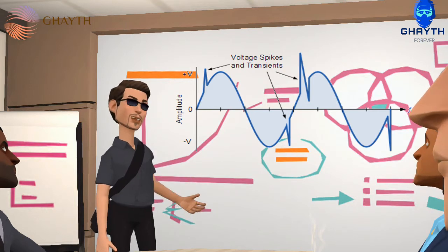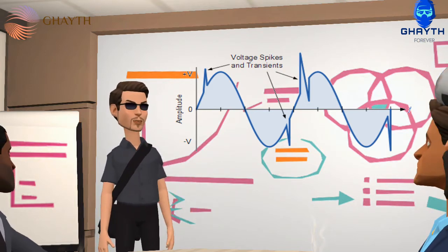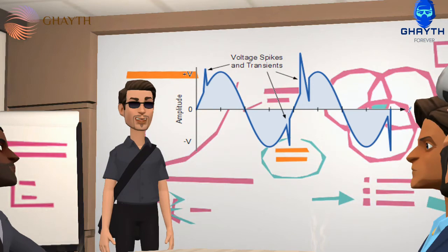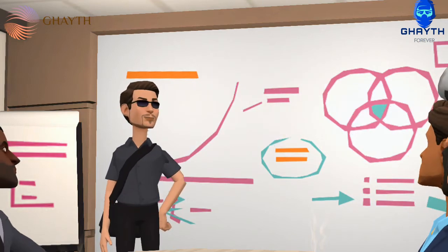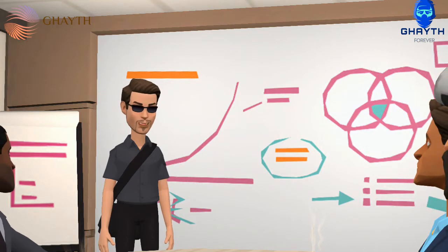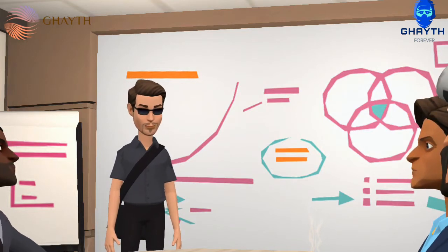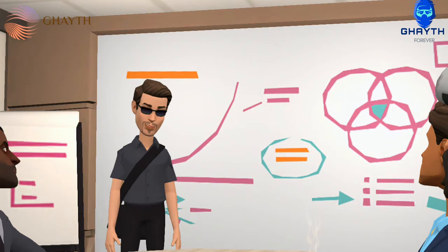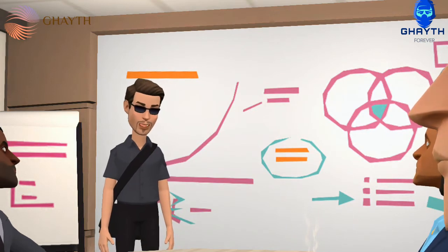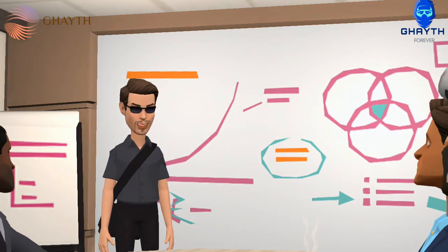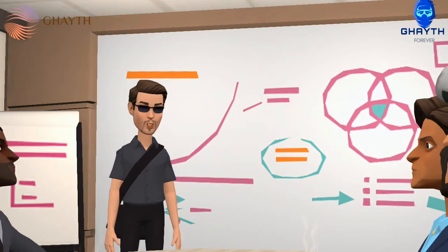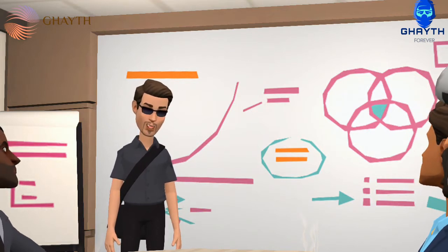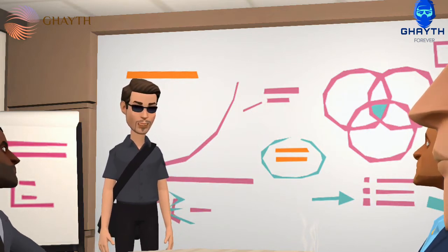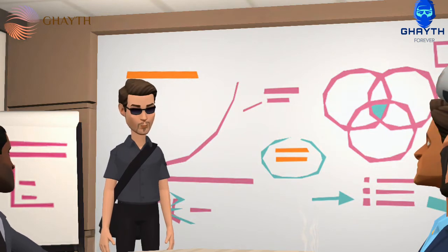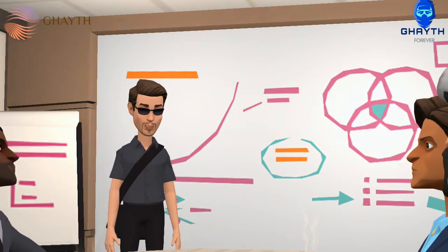However, those nanoseconds, just billionths of a second, can inflict some major damage on a machine if the surge is high enough. What usually causes a surge or spike? One of the most known causes is lightning, although it is very uncommon. More common causes include the operation of high-powered devices such as air conditioners, elevators and refrigerators. The compressors and motors within them require a lot of energy to switch on and off. When switching, it creates sudden, brief demands for power, thus upsetting the current steady voltage flow.